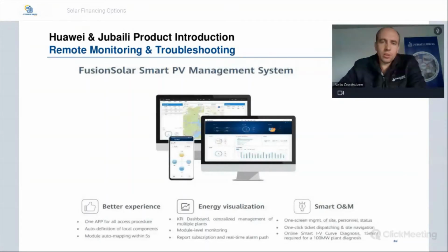And then also you've got the smart operation and maintenance, where you've got one screen for management, where you can see what errors are on the system, possible solutions to fix those errors, or if it's a simple error, as easy as clearing it. And then another feature is our online smart IV curve diagnosis. So on a big 100 megawatt plant, you can scan the whole plant for possible issues in 15 minutes, and you can do it all remotely. You don't need to be on site paying an engineer or a technician and have specialized equipment. All of this can be done remotely.